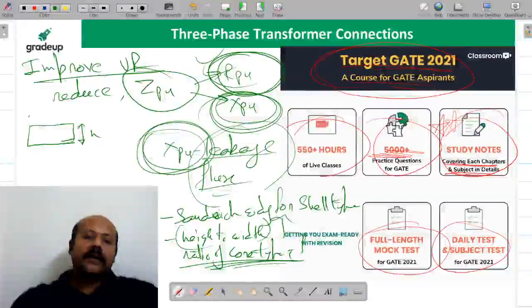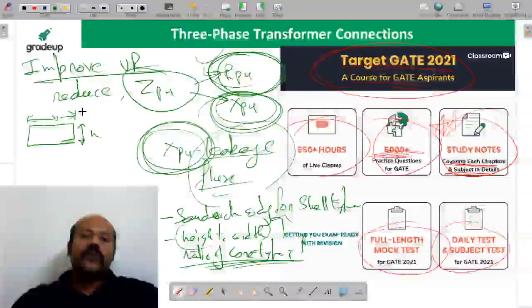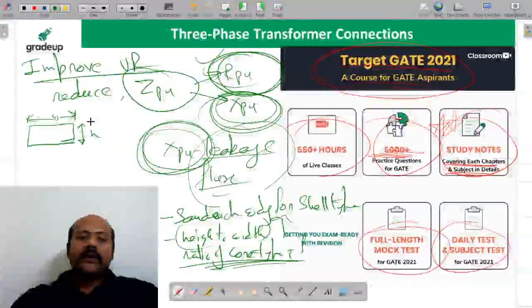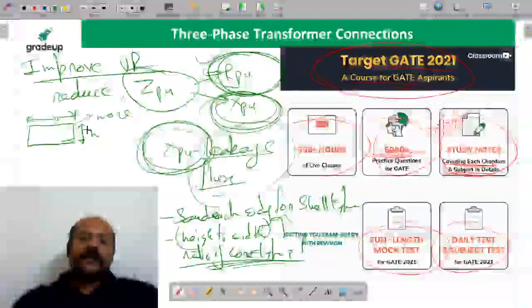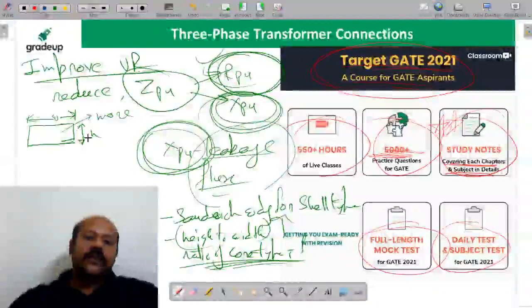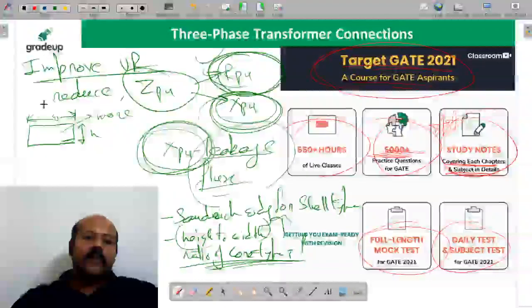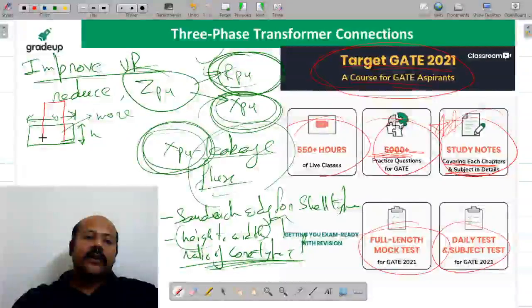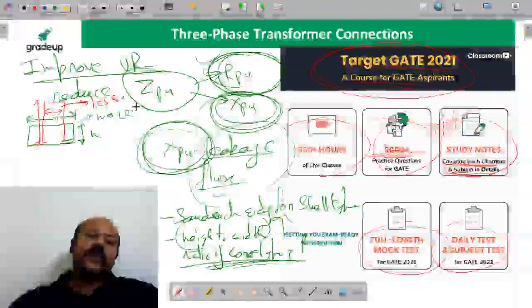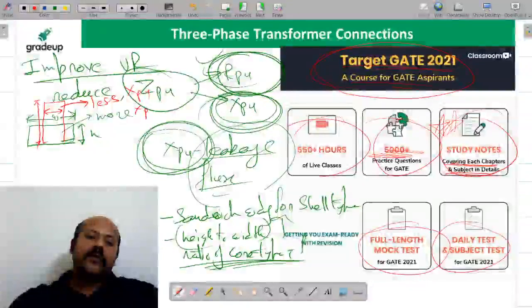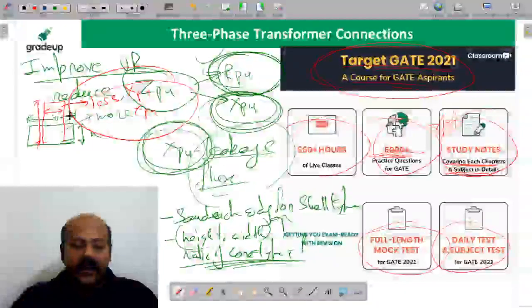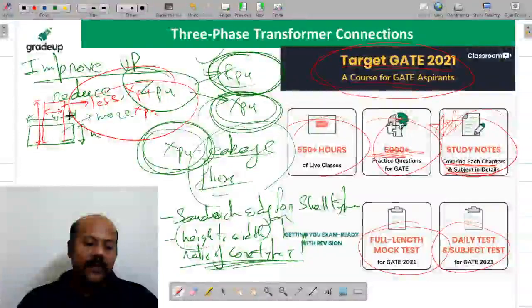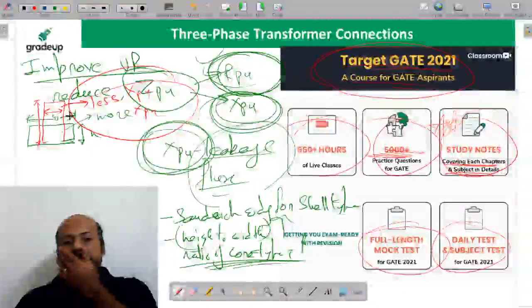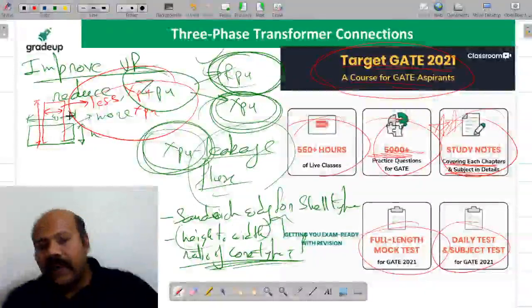This is the height and this is the width of the core type transformer window, so there is going to be more leakage flux. But if you increase the height and reduce the width, there is going to be less leakage flux. I hope you are getting this. So there are different ways to reduce the leakage flux, so that you get a lesser value of voltage regulation.